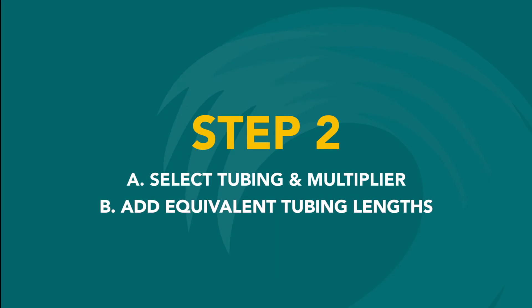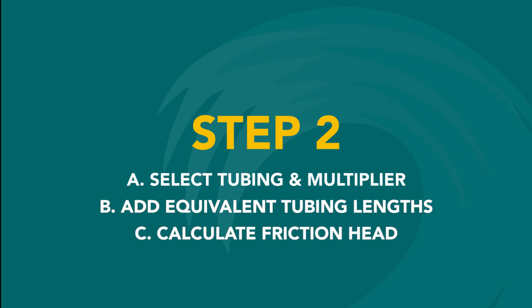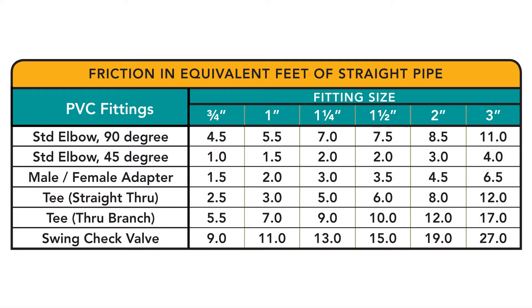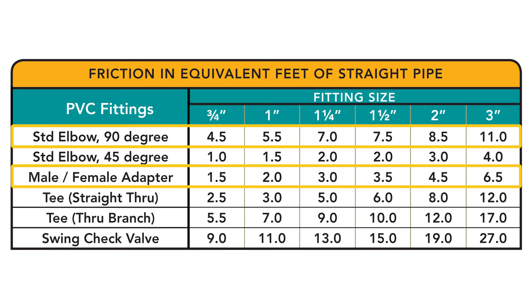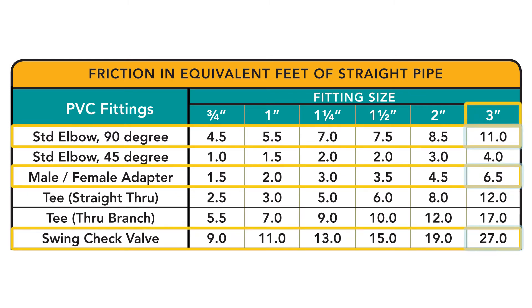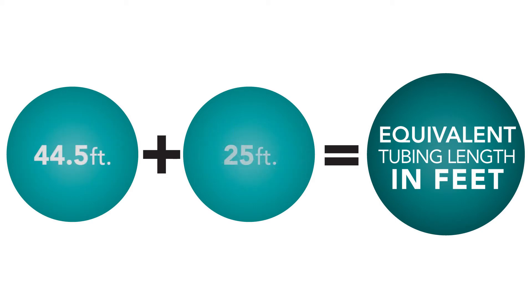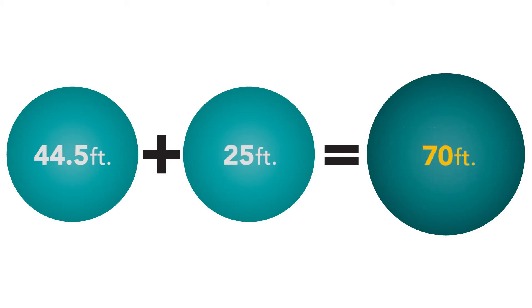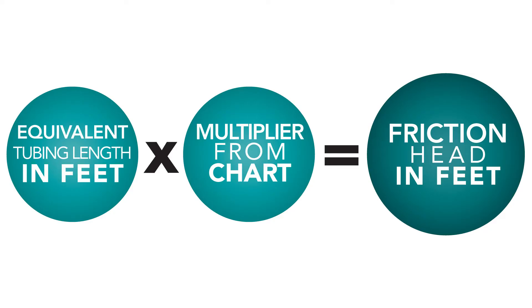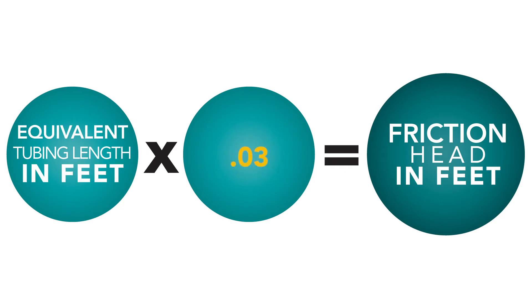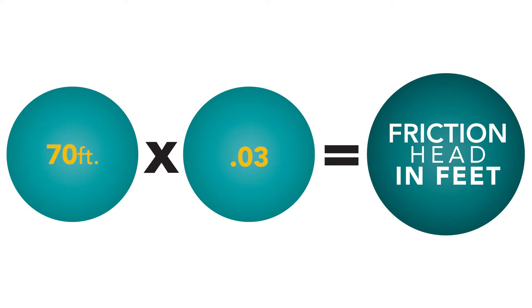Next, we'll add up the equivalent friction loss for our fittings from the friction in equivalent feet of straight pipe chart, and calculate the friction head. If our system requires one 90-degree elbow, one male-female adapter, and one check valve, all 3-inch in diameter, we add together 11, 6.5, and 27, totaling 44.5 feet of equivalent length. Add that to the original tubing length of 25 feet and round up to find a total equivalent length of 70 feet. Multiplying 70 feet by our multiplier of 0.03, the friction head in the tubing and fittings is approximately 2 feet.